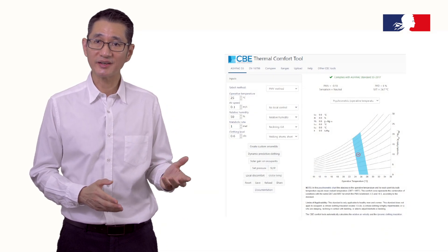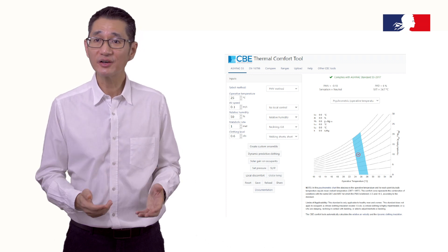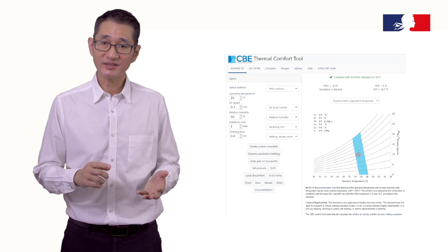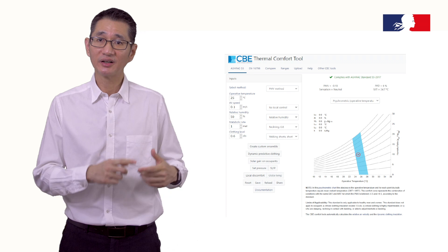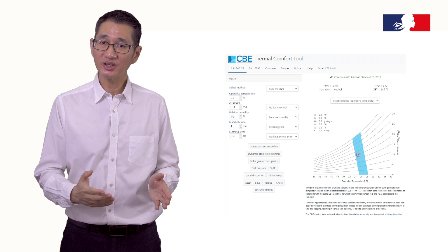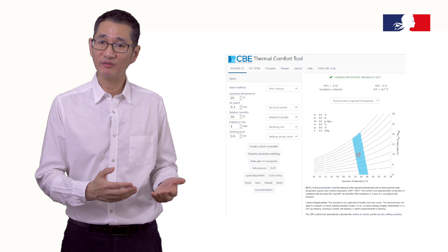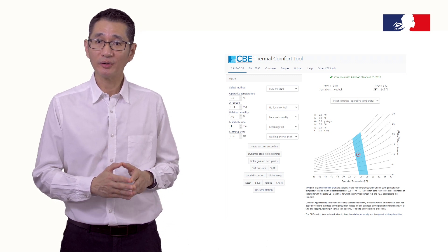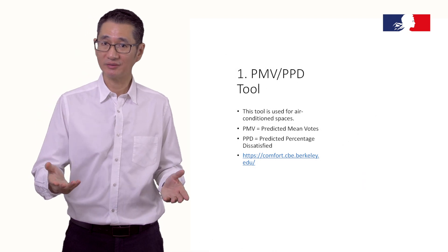The first tool to be introduced is the PMV PPD tool, used for air-conditioned spaces like an office. This tool is very comprehensive and involves heavy computation — it addresses air temperature, air speed, mean radiant temperature, relative humidity, type of clothes worn, and type of activities. Computation is done by computers, and there are many websites offering PMV PPD calculation. One of the more popular ones is provided by Berkeley — do visit it and give this tool a try.